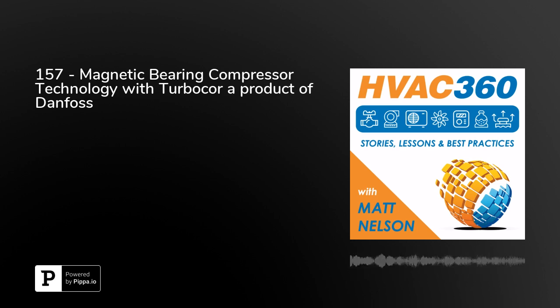Wow. Now, like you mentioned, there are multiple Turbocor compressors typically on any specific piece of equipment, whether it be a chiller. What sort of redundancy does that allow? That is a very good point. A lot of our OEMs have been very successful because, let's say they're bidding on a job and the job requires a redundant chiller. What our OEMs have been able to do is say, you can actually save money because you don't need an additional chiller for redundancy. We can provide redundancy by having multiple compressors on the same chiller. So if there is an issue with one particular compressor, the other compressors can still deliver not necessarily the full load, but the majority of the load or the cooling capacity that would be required. So in certain situations it helps you save without having to buy an additional chiller, and you have the redundancy as part of the compressor.